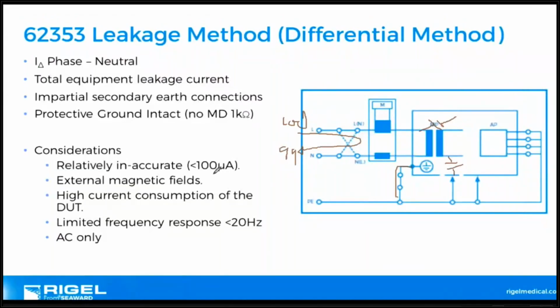It does have some benefits. The benefits are that you're measuring the total equipment leakage. It's impartial to secondary earth connections, which I'll go into later. And we do have an intact ground, so there's no 1K body model impedance or that reactive circuit that I showed earlier on. It does have some considerations because of the nature of how it's measured. This measuring circuit here, the accuracy isn't particularly great under certain amounts of current. It can be affected by magnetic fields, and if you have a lot of current, let's say rather than 100 milliamps, this is 10 amps, then you might have a problem picking up some of the measurements.